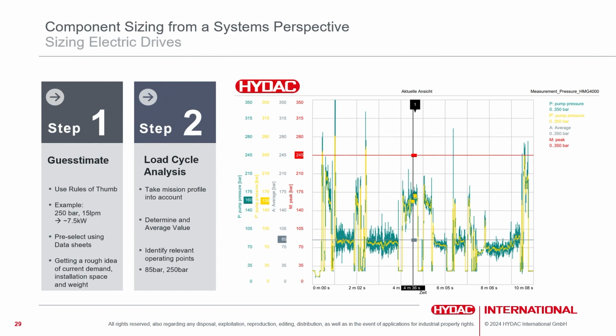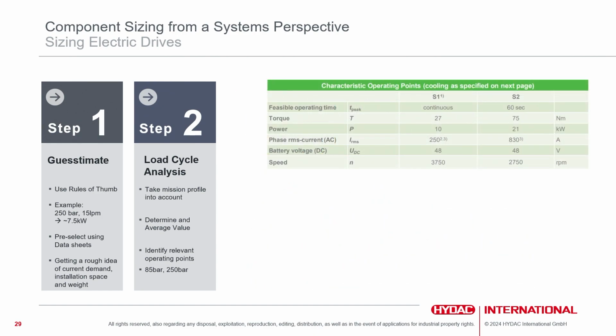And with those 2 operating points, we can go back to the data sheet and find out that 85 bars is really the average. So the continuous 10 kilowatts of the motor might be way too big, because 85 bars is a third of the 250, so we're roughly talking about 2.5 kilowatts. So why choose that 10 kilowatt motor? We should take a closer look.